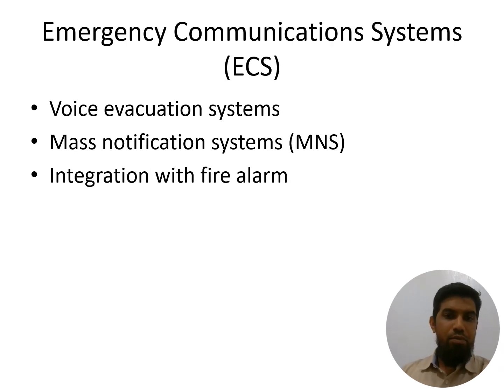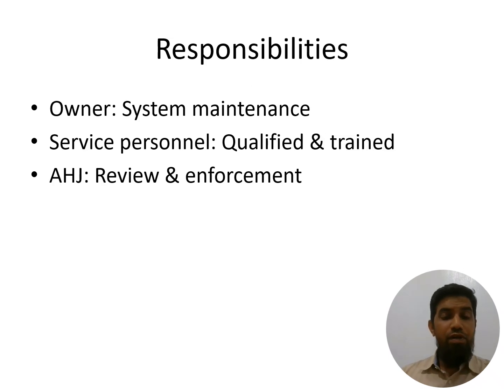Well, here in this slide, emergency communication system. Emergency communication systems generally cover voice evacuation systems and mass notification systems, and they integrate with the fire alarm system. In this slide, we will discuss the responsibilities for the fire alarm system. Usually, the owner is responsible for system maintenance. The service provider should be qualified and trained, and the authority having jurisdiction usually reviews and enforces the codes and standards. Whereas the designer ensures the system layout complies with NFPA 72, and the installation contractor follows the approved drawings and the manufacturer recommendations.